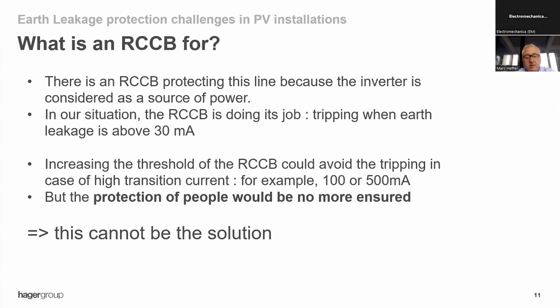Increasing this threshold of the RCCB, you know, there are RCCBs with 100 milliamps or 500 milliamps, even more. This could avoid the tripping in case of high transition current. But of course, the people would not be protected anymore. So changing the RCD to put a higher threshold is not a solution. It cannot be a solution in this case.